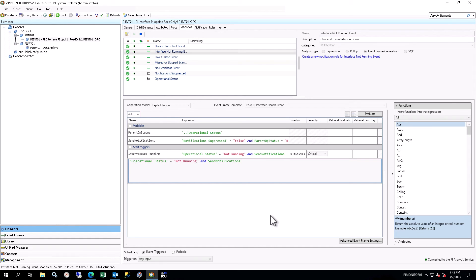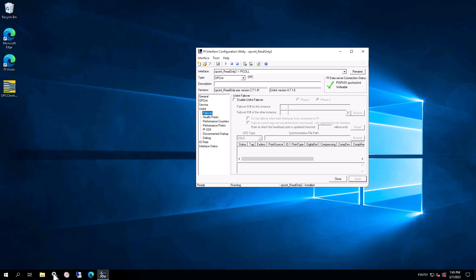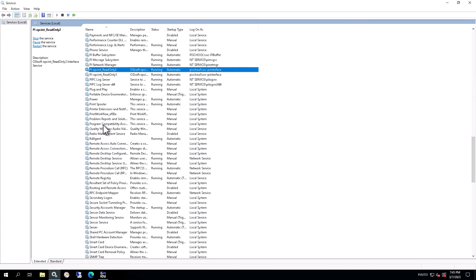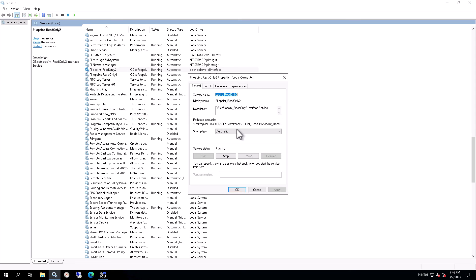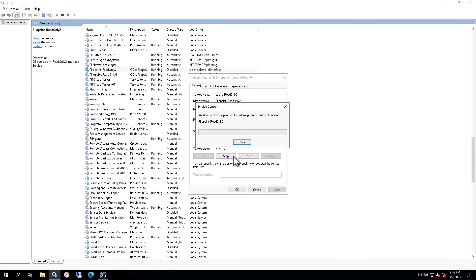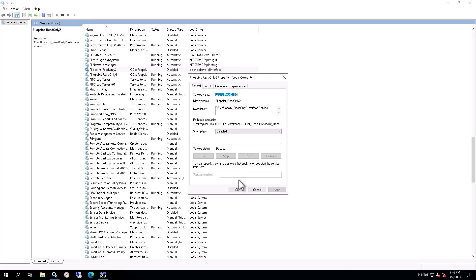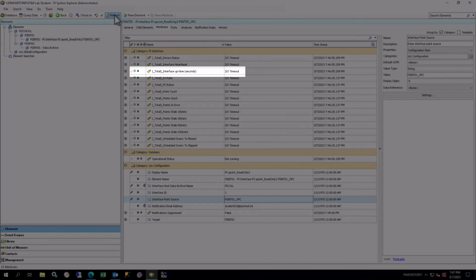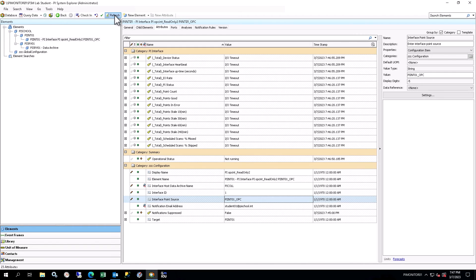Remember the value you entered for the DisplayName attribute on the Interface Instance element — you will need this. Return to your connection for PIINT01. On PIINT01, open the Windows Services pane via the icon on the taskbar. Find the service that matches the DisplayName for the Interface Instance — it should be running. Right-click on the service and select Properties. Set Startup Type to Disabled and click Apply. Then click Stop. Confirm the status shows blank, indicating that the interface is no longer running. Back on PI Monitor 01, in PI System Explorer, click the Refresh button and confirm the value for the TotalInterfaceUptimeSeconds attribute shows as IOTimeOut, indicating that no values are coming for that tag. All other monitored tags will also show IOTimeOut when the interface is fully stopped. Operational status should show as not running.